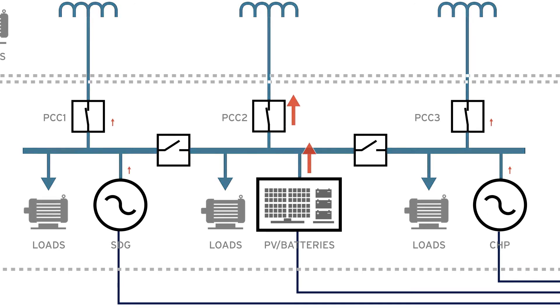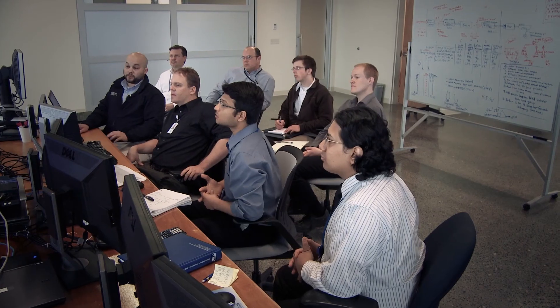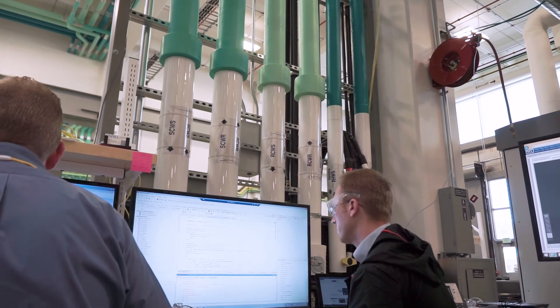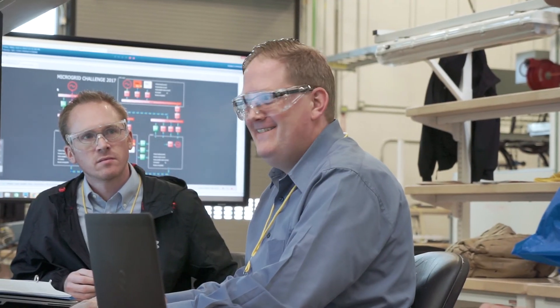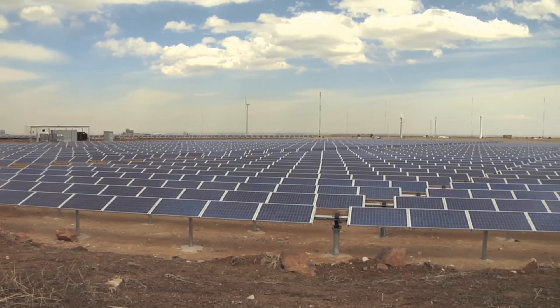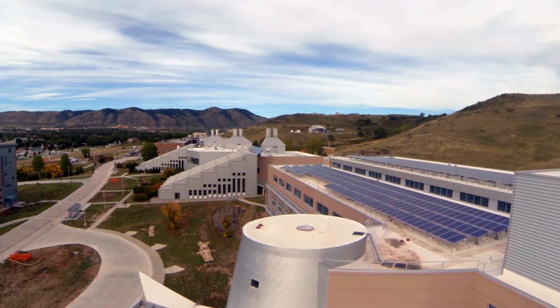When the SEL controller took over the microgrid and transitioned away from the utility, they proactively closed a lot of the tiebreakers and the distribution lines between all the different areas. That allowed them to better serve some of those critical loads regardless of which local generation assets were still available. We put together a team that really comprised the right expertise, and that's something that makes SEL's team successful on microgrid projects. It's really exciting to be on the forefront of the energy systems transition and working with really smart people to develop our future energy systems.